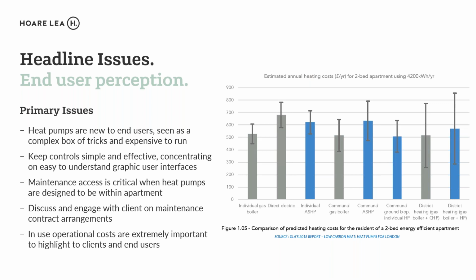Maintenance space within the utility cupboard and around heat pumps is something that needs to be considered. And also maintenance contracts. And I'll come on to the issues with dispersed heat pumps within residential units rather than sticking with central. Because we are seeing that with the energy loop solution, you end up with in-apartment heat pumps, we need to then agree how heat pumps are maintained, whether it's by the tenant or on a group collective basis in regard to a tenancy, an apartment ownership of the block, as to how to set up maintenance contracts.